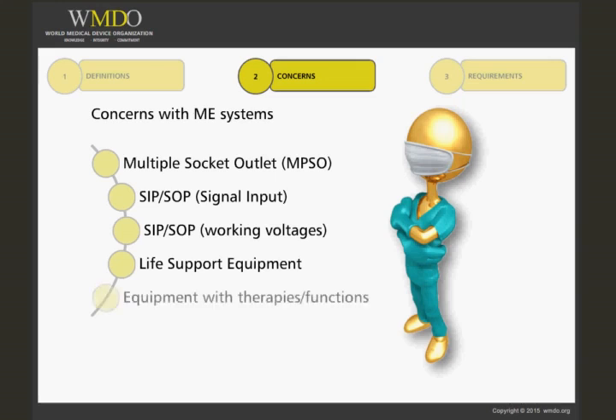Finally, equipment or systems with therapies or functions that could affect one another must be considered, such as multiple alarms and different radiation levels. You don't want alarms that confuse the operator because they cannot determine which part of the system the alarm is coming from.